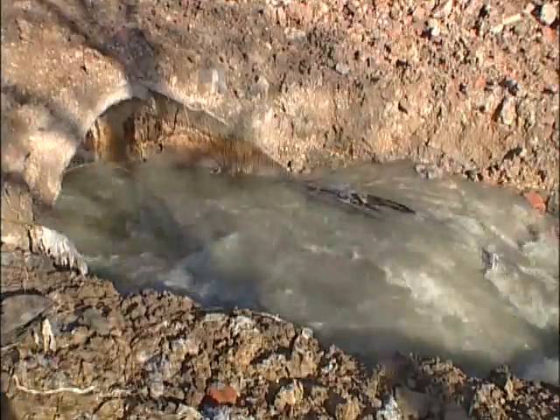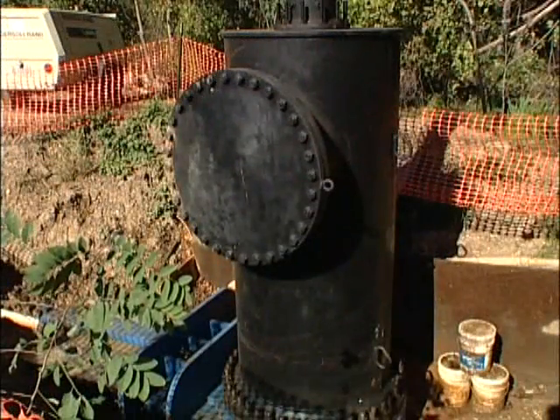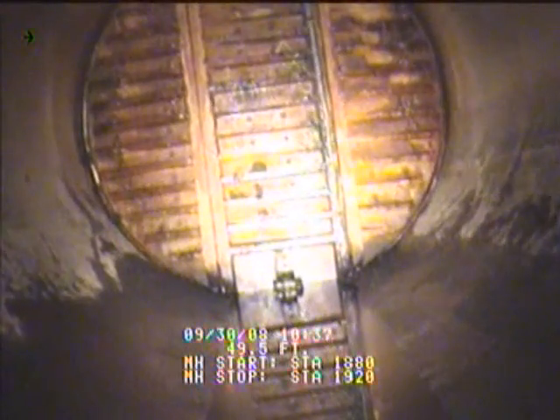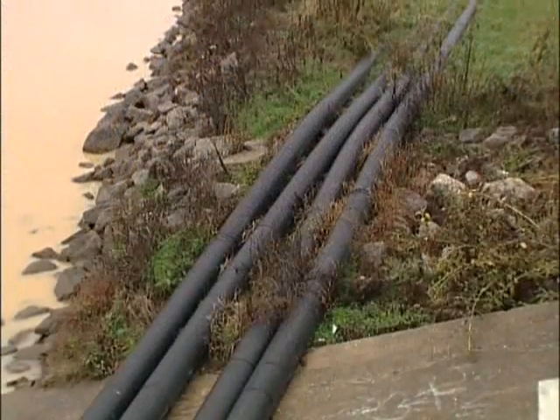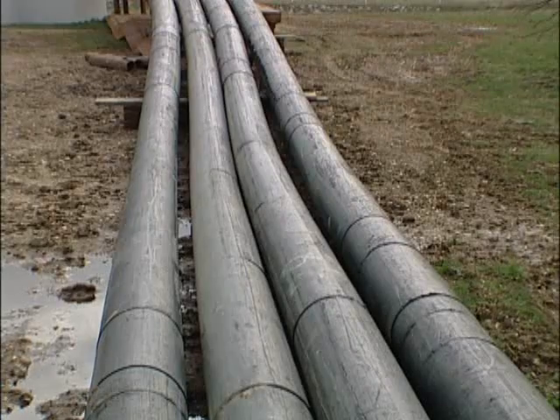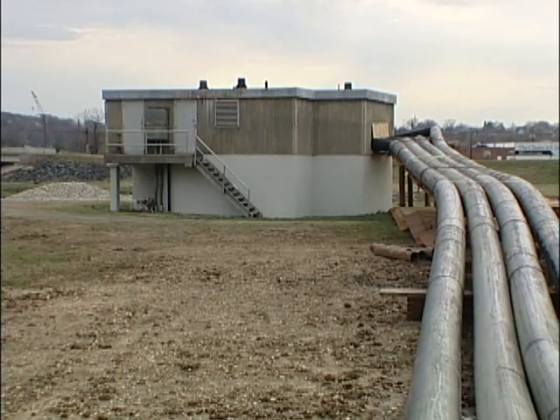The sluice gates posed a problem — they simply wouldn't work. By late winter it was on to Plan B: installing line stops, which are temporary valves. These are not easy items to install; we'd never done it on a sewer main, so it was a new process for us. By July, the line stops were in and five powerful pumps ran the massive maze of bypass — likely one of the larger line stop installations in the country. We have four 18-inch sections of pipe, approximately 2,000 feet apiece, running all the way underneath Rhode Island Avenue and the CSX railroad tracks to Junction Chamber 2.